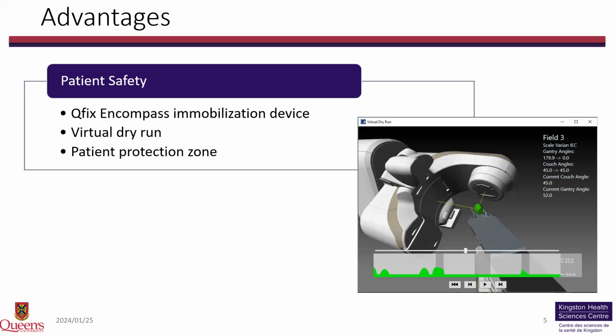In terms of patient safety, the HyperArc treatment technique provides a collision check when you are planning the HyperArc treatment. This collision check provides a check to prevent any possible collision between the patient, gantry, or couch and gantry. So there is a predefined patient protection zone in HyperArc treatment. In terms of the treatment planning, this patient protection zone is defined as the allowed limit for the placement of the isocenter. So if the isocenter of the treatment is within the patient protection zone, then we can consider the automated delivery of the HyperArc treatment will be collision-free.